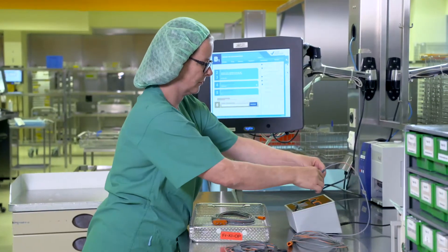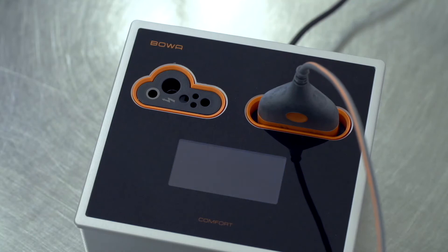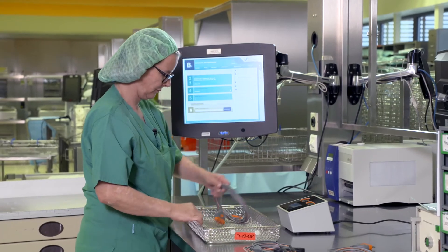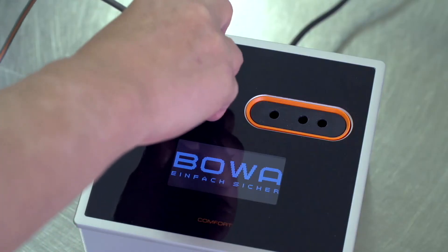All uses of the instrument are automatically saved in the integrated RFID chip. The BOWA Comfort Box reads the chip, thereby ensuring seamless documentation and observance of the maximum number of usage cycles. With the BOWA testing device, every cable can be tested individually.